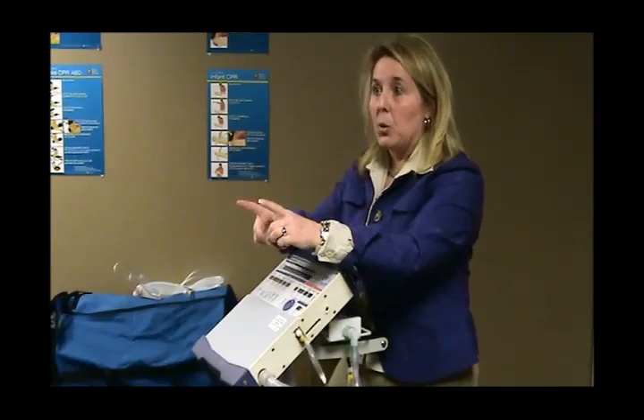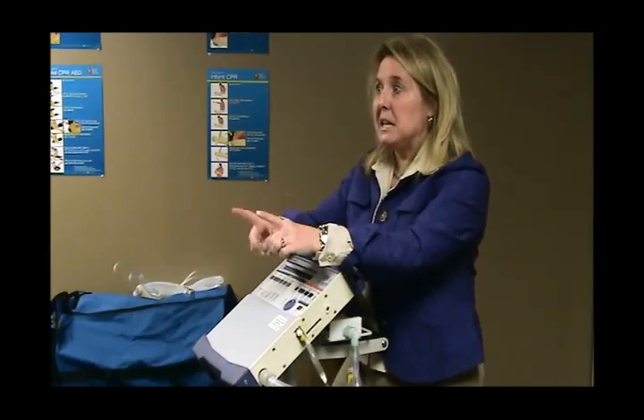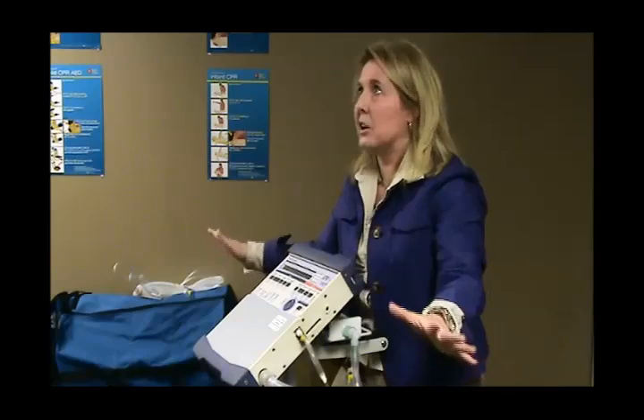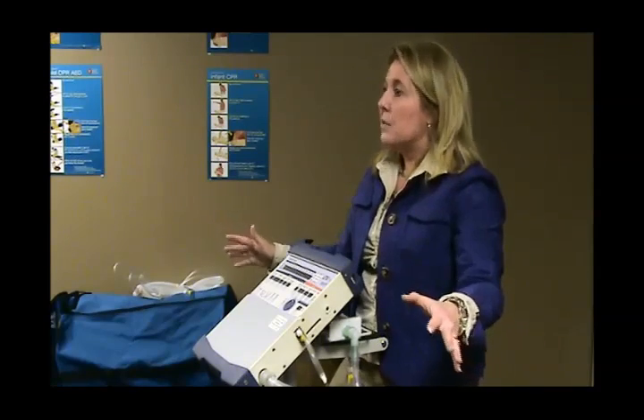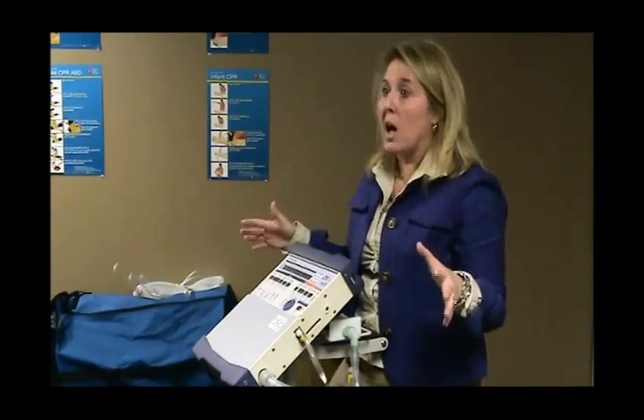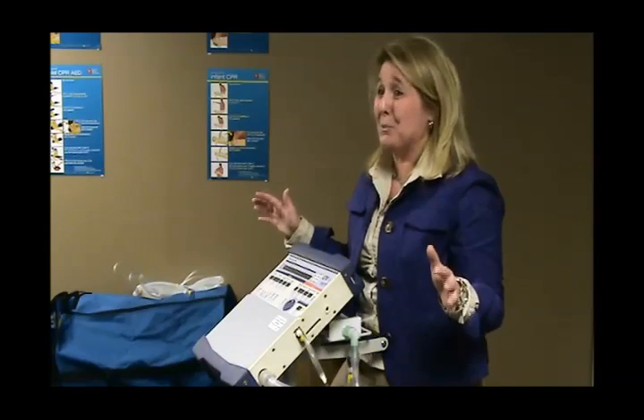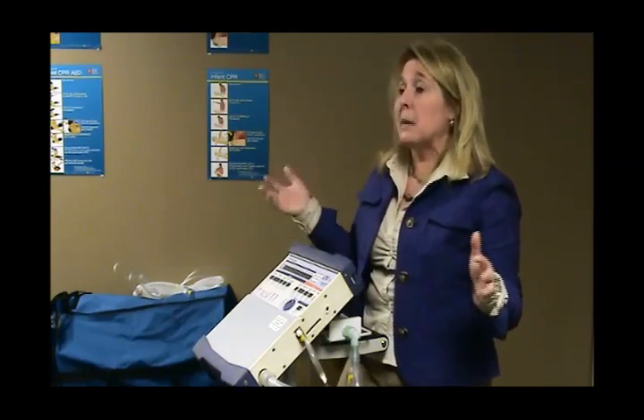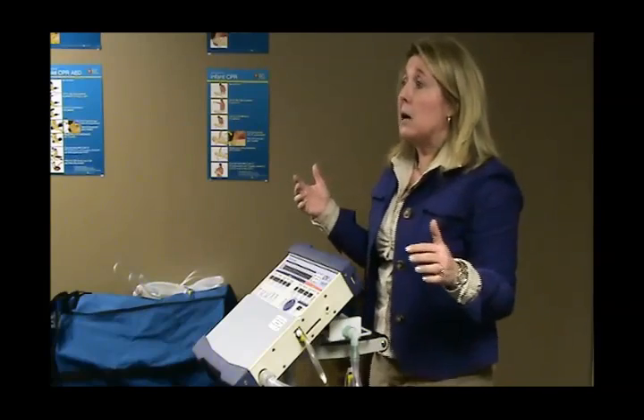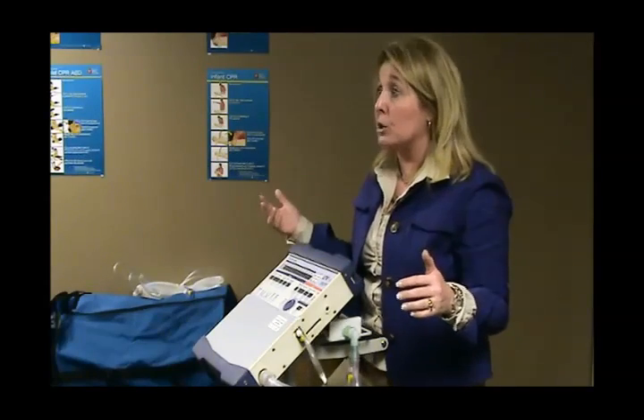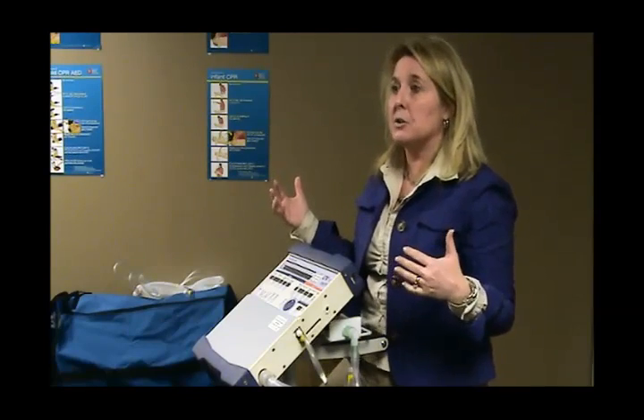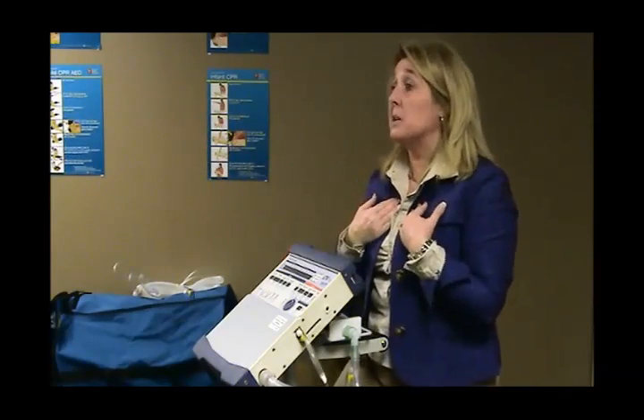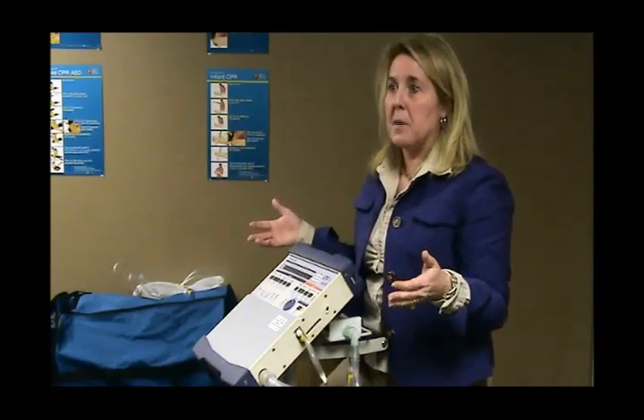We have obsoleted those old ventilators. That does not mean that if somebody is out there on one, that they have to get off of it right away because it's been obsoleted. Those ventilators are very durable, and they'll run past our support date. They've been obsoleted now for about 2 years. The company will continue to make parts for them. The FDA requires that it be 7 to 5 years. So we've got at least 5 more years left on those ventilators. So nobody has to go, oh my gosh, we've got to get off this ventilator. What I recommend to people is, ventilators have to have preventative maintenance.